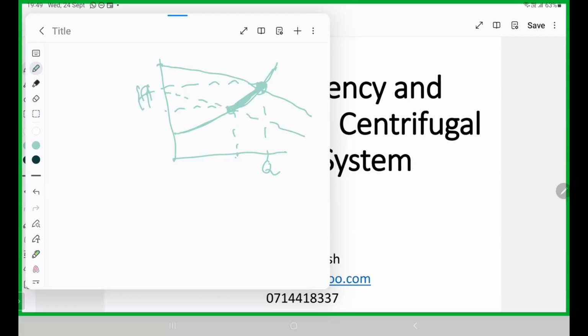But ideally, this is the ISO efficiency curve. If you use this one, the efficiency is different. This one is higher. Generally our selection point is a higher efficiency point, but with variable flow rate, the efficiency is somewhere here, right? Then you have to think about what our flow rate is, how frequently we use this one, or what the average flow rate is, and what the efficiency drop is if you use this one.